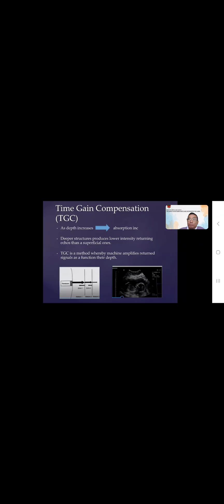So how do you overcome this? You can do a few maneuvers. You can increase the gain, or the emitted ultrasound strength can be increased in a particular area. This is called time gain compensation. You can increase the beam strength emitted by the probe so that the reflected ultrasound beams also come back with much higher strength. Or you can amplify the returning, or reflected, ultrasound beams with the transducer so that you can visualize in more detail. Okay.